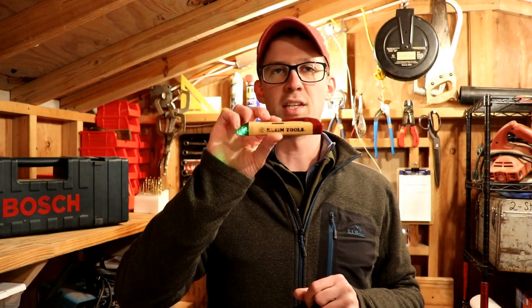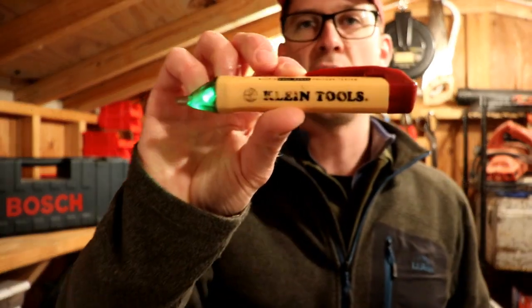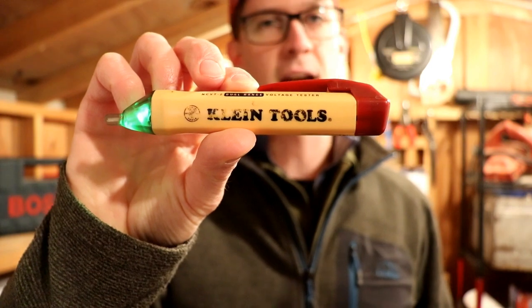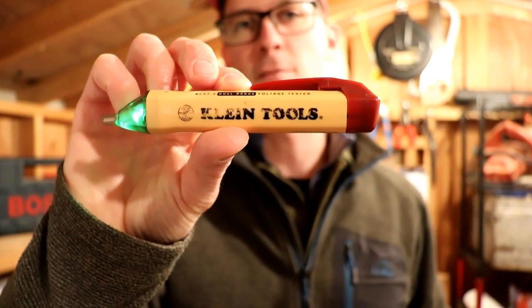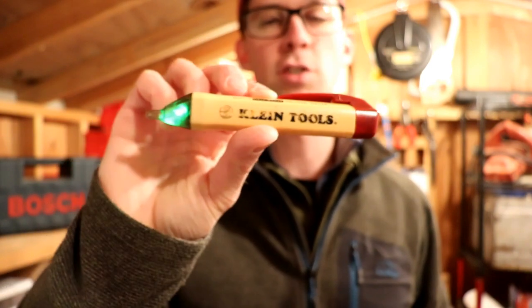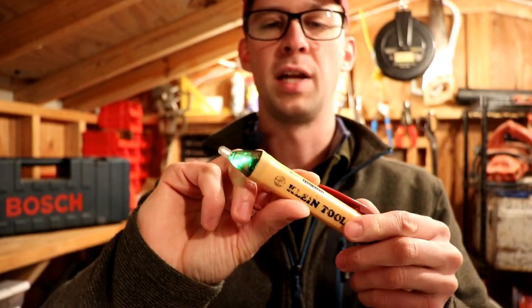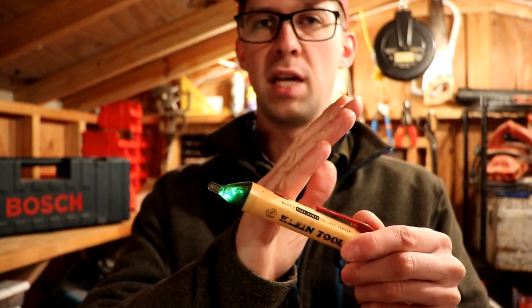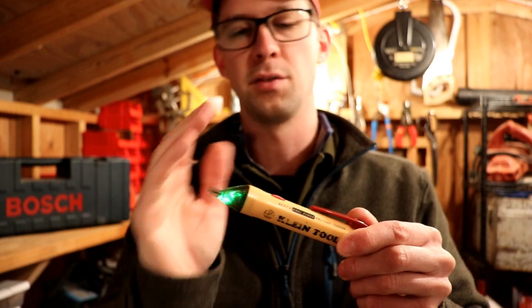Let's take a look at this exact tester. This is the Klein NCVT-2 — that's non-contact voltage tester, dual range. Let's start by looking at the higher range. This will do from 12 to 48 volts and from 48 to 1000 volts.